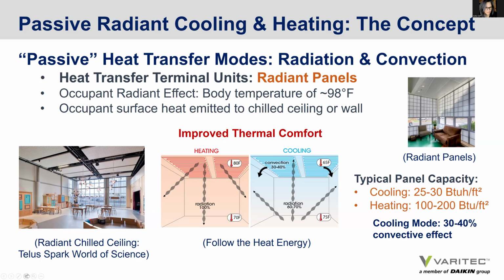So radiant panel technology can offer up to 25 to 30 BTUs per square foot of ceiling panel in cooling and up to 100 to 200 BTUs in heating. There is also a convective effect on radiant panels in cooling mode. The air adjacent to the panel surface is cooled via conduction, and that air will drop into the space normally. And so you do have convection occurring with these devices as well, offering some supplemental cooling effect.